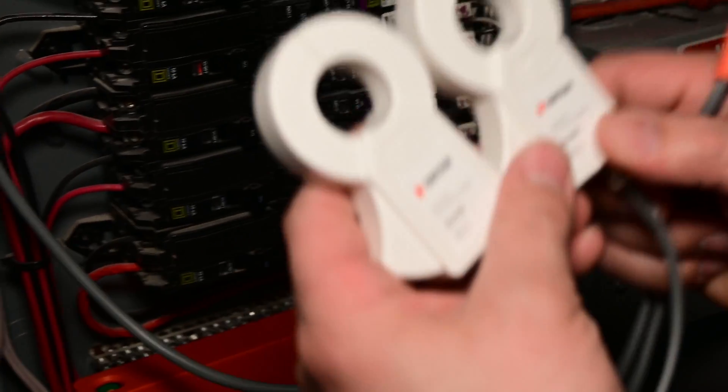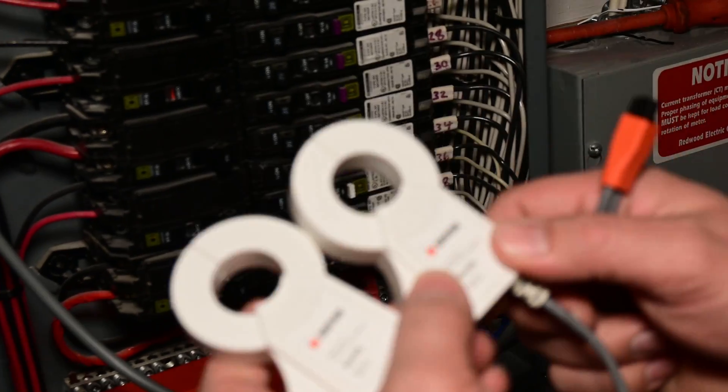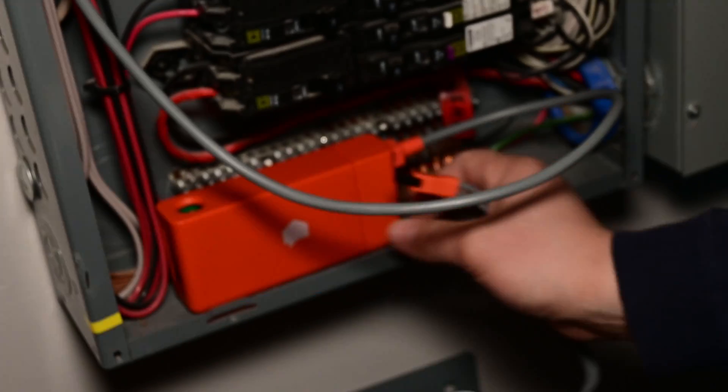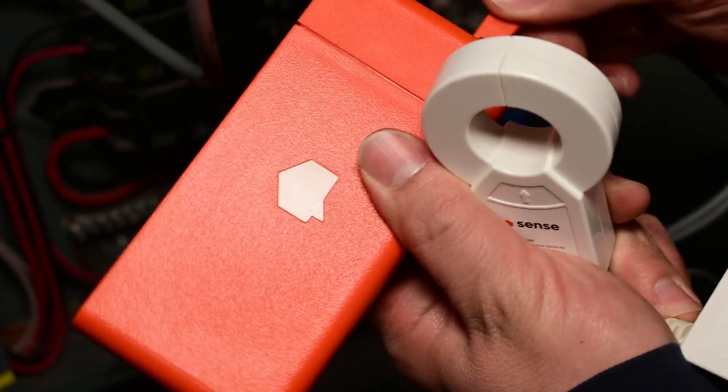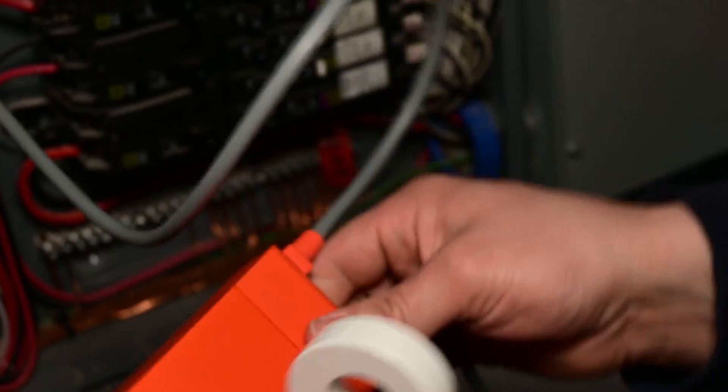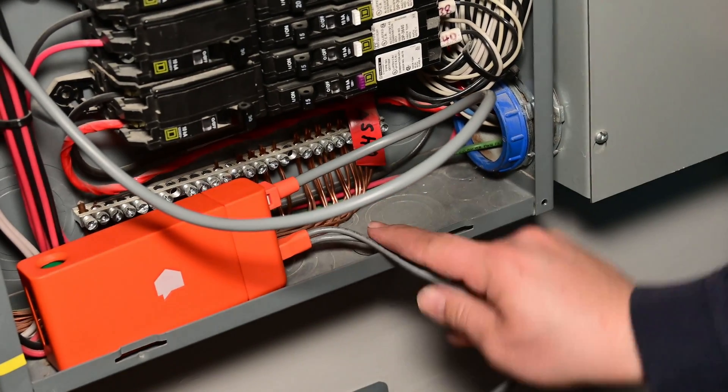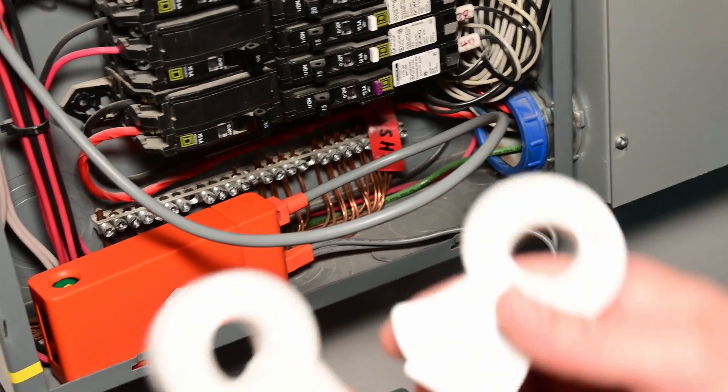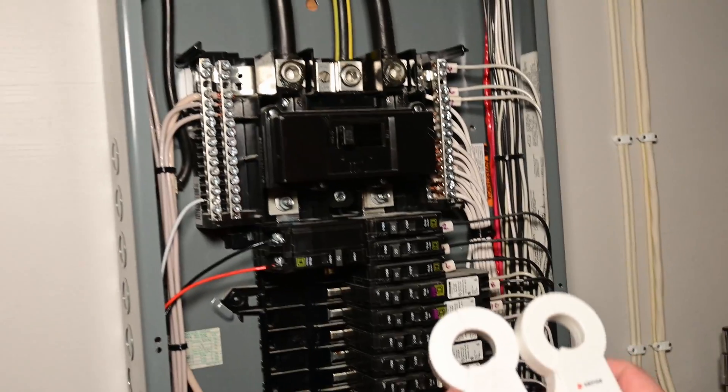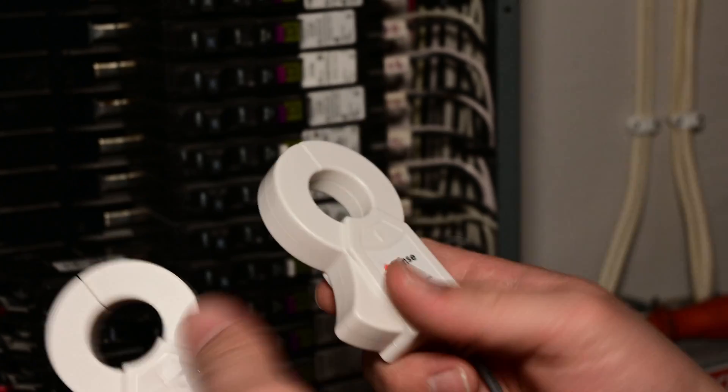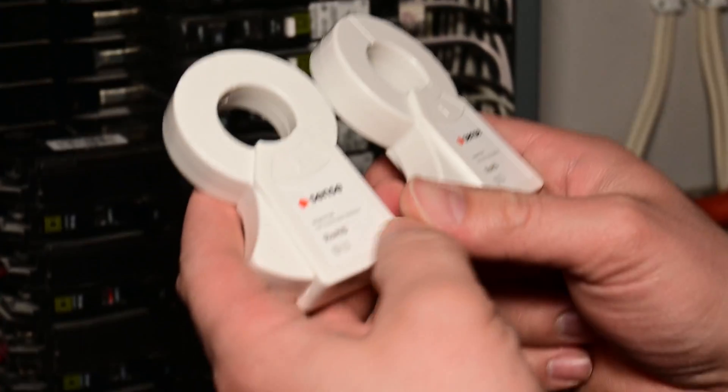Now we're going to install the amp meters themselves up on where the service cables come into your panel. But before we do that, we're going to connect them to the energy monitor for safety reasons, according to the instructions. I'm guessing it's just so that there's a path to ground that's connected while you are working with these. Now, you can see that they have these stickers on one side, and on the opposite side they do not. You just need to make sure that the side with stickers faces the same direction for both clamps, preferably up like this.